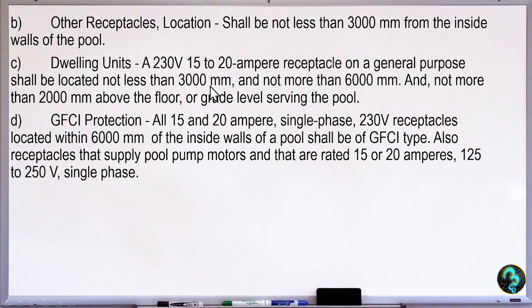So if in case yung bahay natin may swimming pool, so ito yung mga tawag doon, mga requirement for a receptacle or an outlet. So dapat hindi siya bababa, ang location niya is not less than 300 mm. Tapos hindi naman siya ano 6 meters or 6000 mm from the pool. Tapos vertically pataas, so that is 2,000 mm above the floor or the grade level of the serving pool.